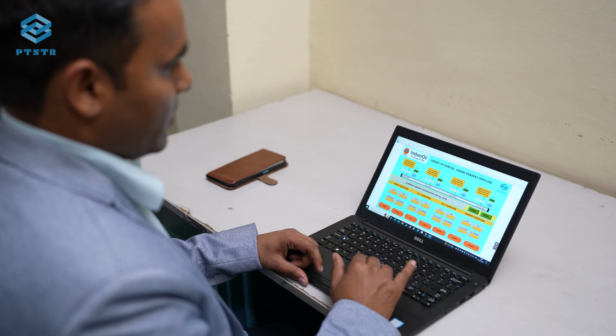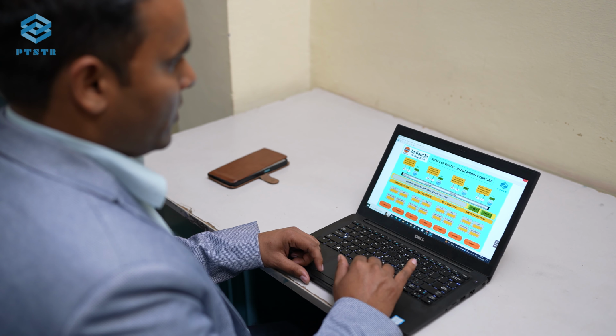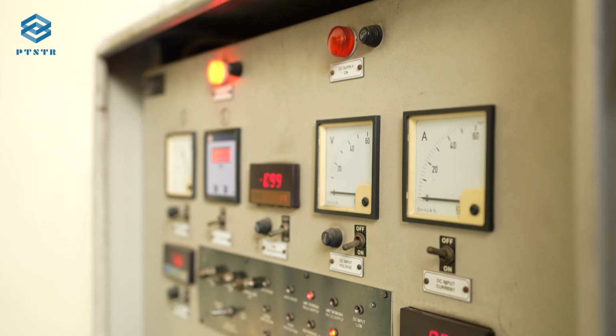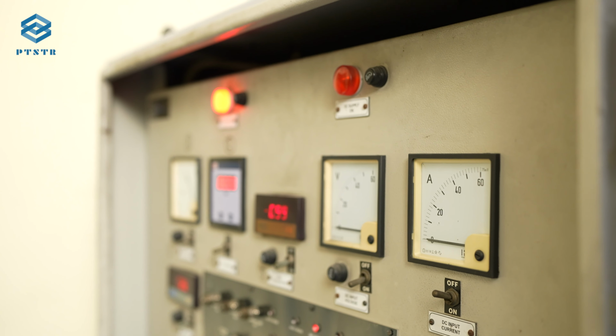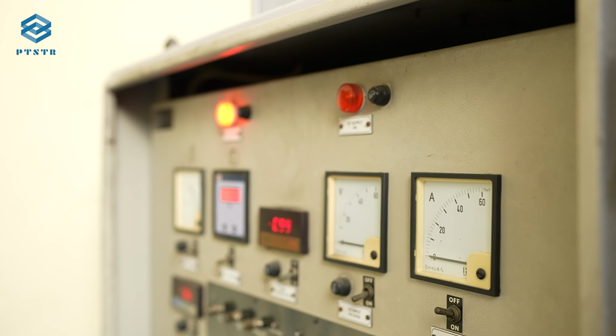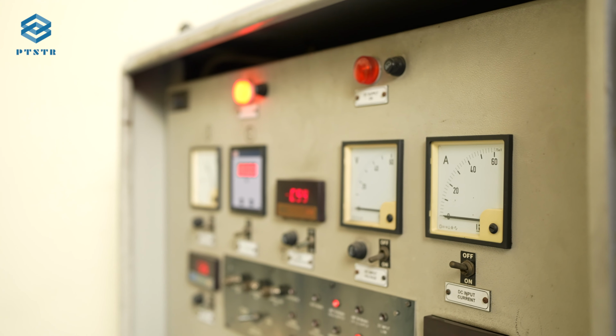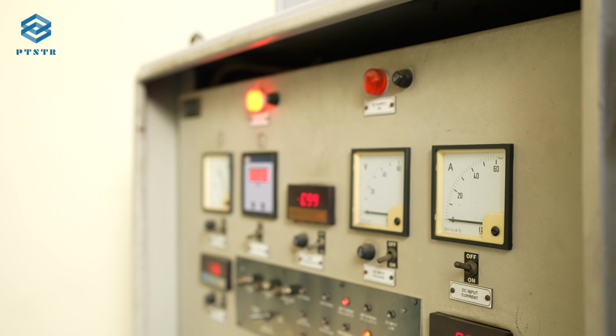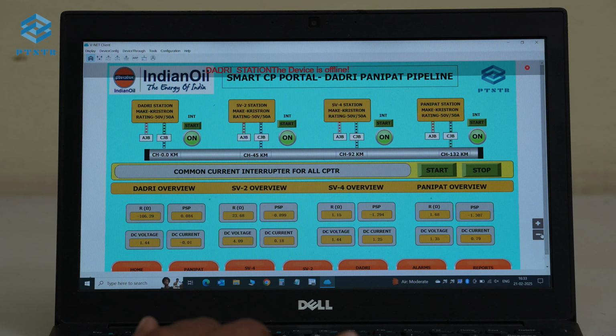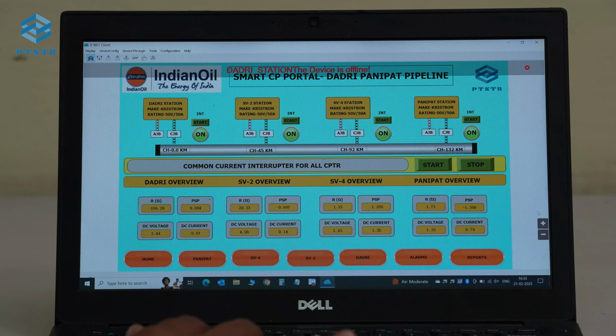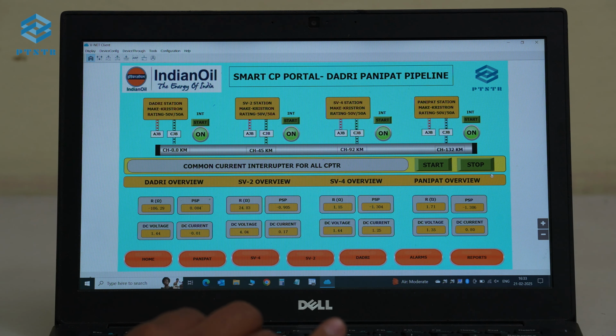We have the capability to monitor live readings of DC voltage, DC current, PSP value, DC circuit resistance, ammeter and on-off PSP of CPTRU, among other parameters. More importantly, we can also control CP parameters in real time, including DC voltage, current limits, internal PSP and current interrupters. This advanced implementation has been introduced for the first time across IOCL.